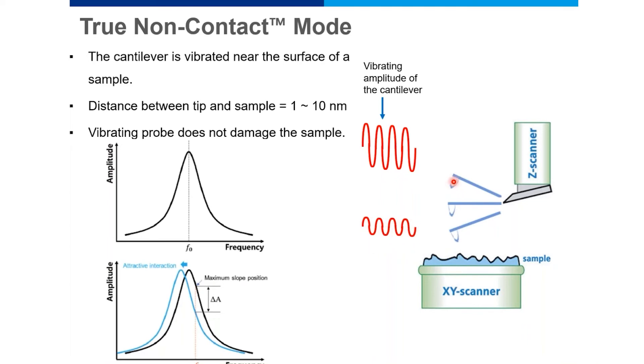Because of the long-range attractive interaction, the amplitude of the oscillating cantilever decreases. When the cantilever tries to come closer to the sample surface, the amplitude changes — the effective spring constant of the cantilever decreases, and the resonant frequency also changes. In non-contact mode, we do not physically touch the sample; we are approximately 1 to 10 nanometers from the surface, and we monitor the change in amplitude of the vibrating cantilever. This change in amplitude is set as the set point to generate an image.